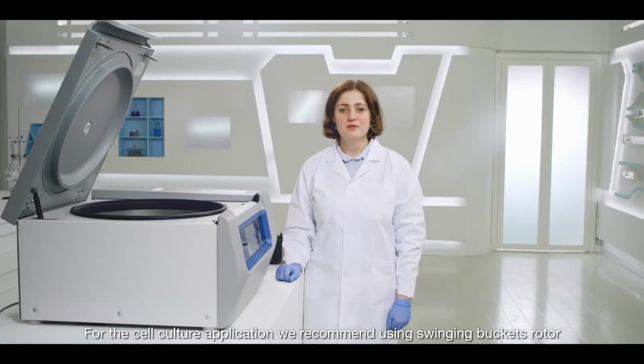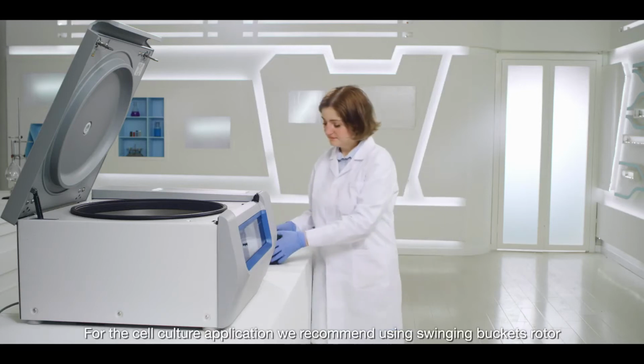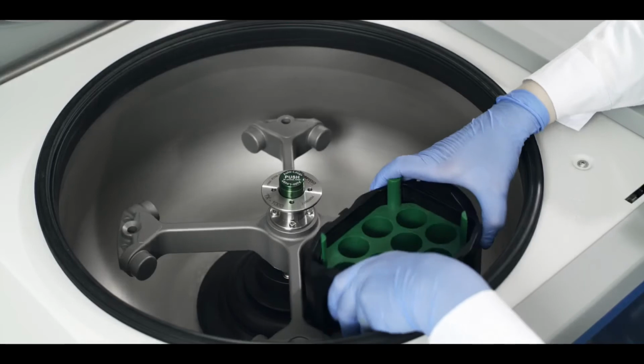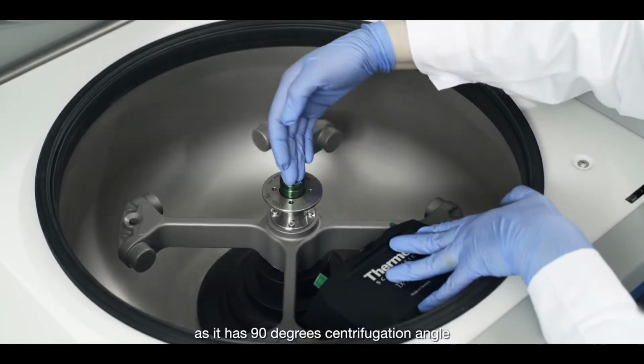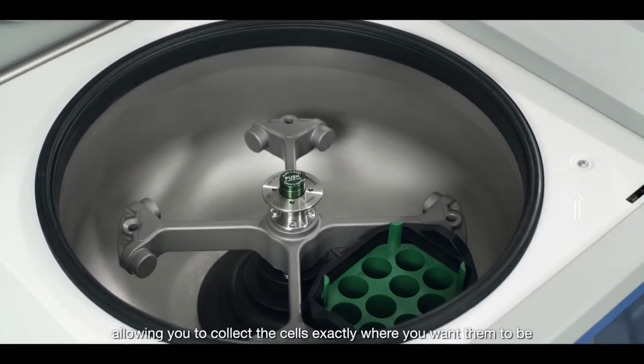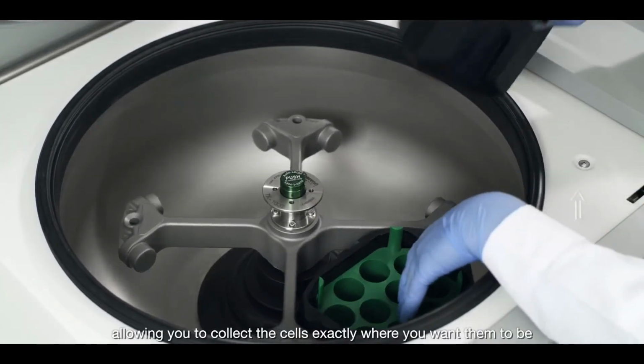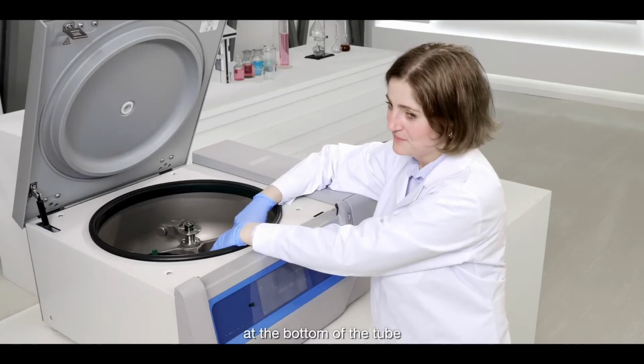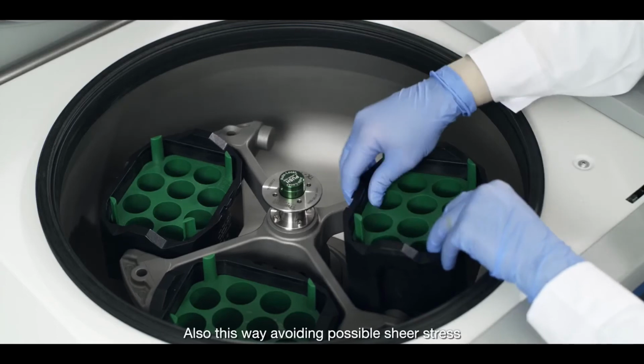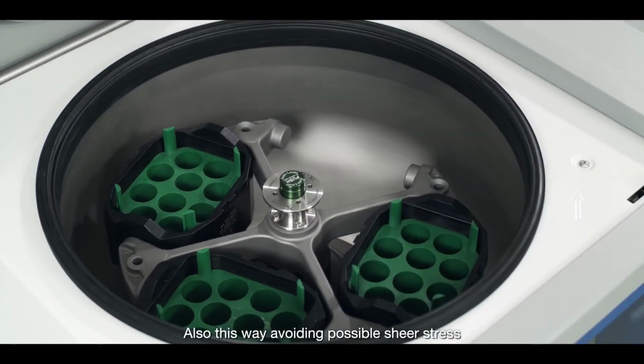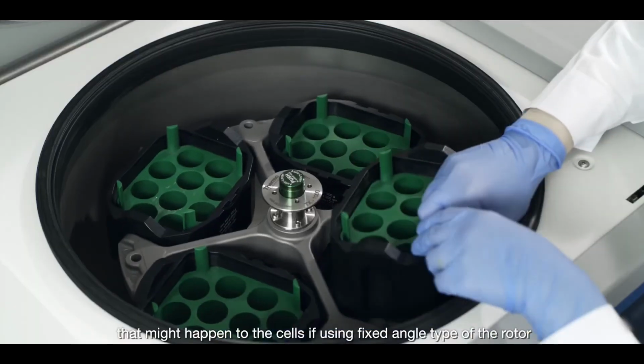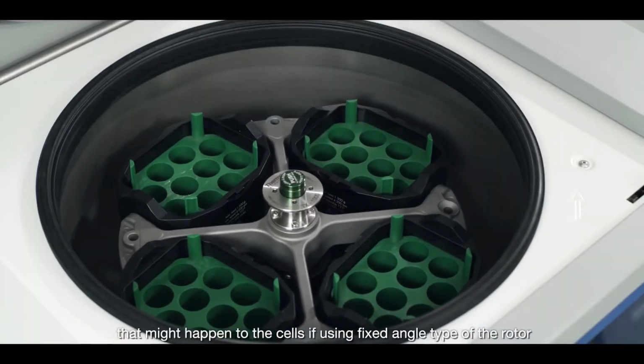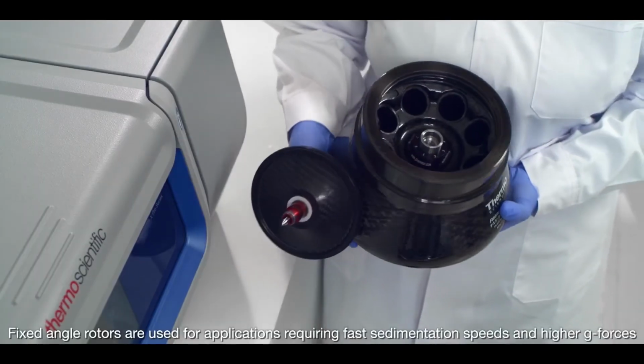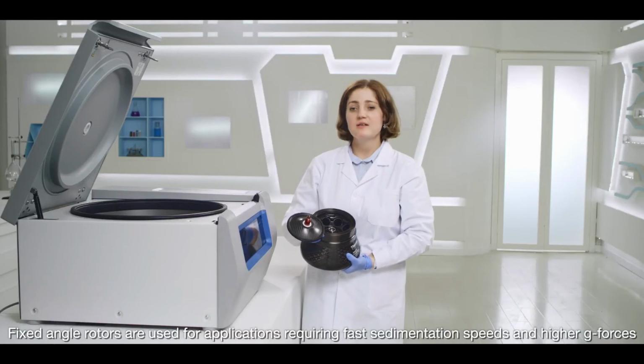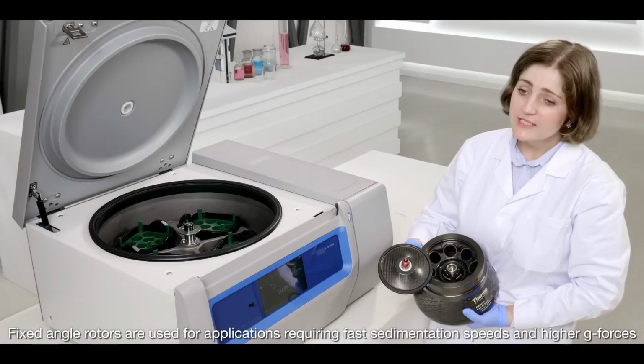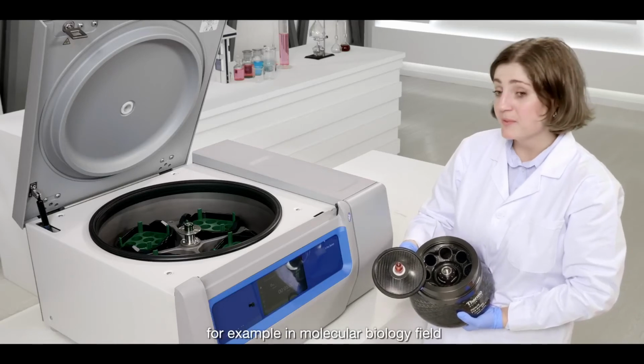For cell culture applications, we recommend using a swinging bucket rotor, as it has a 90-degree centrifugation angle, allowing you to collect cells exactly where you want them to be, at the bottom of the tube. Also, this way you avoid possible shear stress that might happen to the cells if using a fixed angle type of rotor. Fixed angle rotors are used for applications requiring fast sedimentation speed and higher G forces, for example in the molecular biology field.